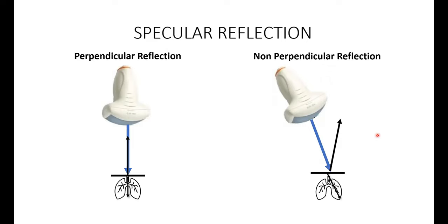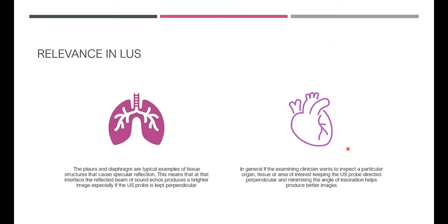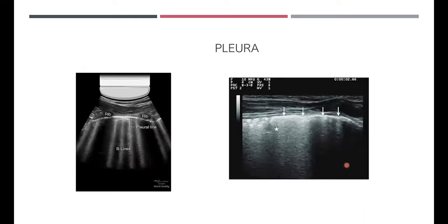So you can see how the ultrasound wave reflected at an angle, because you're not perpendicular, is not going to come back. That means you're going to get less intense images, and there's an element of artifact that you can actually miss if that's the case. What is important is that your angle of insonation is always kept at 90 degrees.